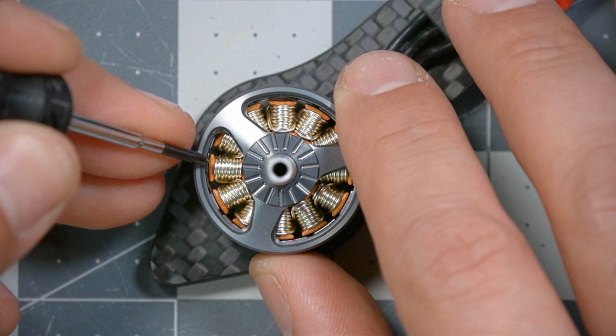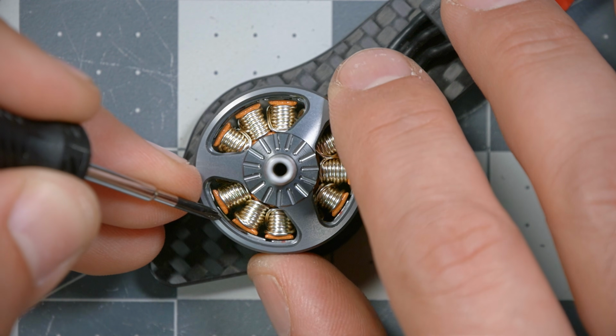Another check is to look at the windings from the top and see if there's any sign of damage, specifically discoloration or burned spots. Sometimes you can also smell it—if you put your nose up to the winding, you can smell the burned enamel. I have had cases where I slightly smoked a motor, but then the motor continued to work fine. I didn't burn all the way through the enamel and it was still functional.